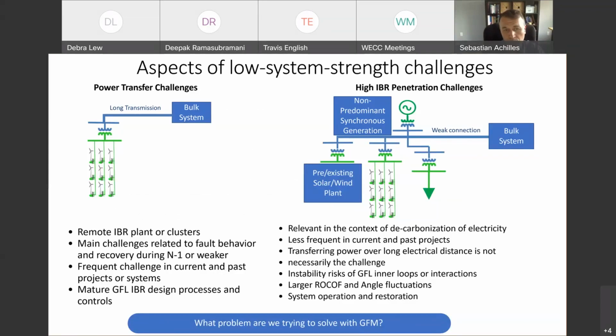The picture on the left represents when you have a large wind plant or solar plant connected at a point through a very long transmission line, so a large impedance to the bulk power system. If you look at the system strength at the point of interconnection, or at the combined terminals of the wind turbines, that system strength is low. Here we're trying to transfer a significant amount of power with respect to the entitlement Nick referred to, and there's a limit to how much power any source can transfer through that long transmission line.